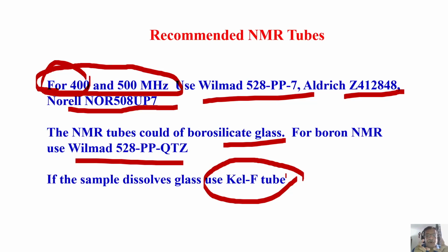You have to use only the identified or prescribed NMR tubes for a particular frequency of the spectrometer. For a particular Larmor frequency, you need to use particular NMR tubes which are prescribed.